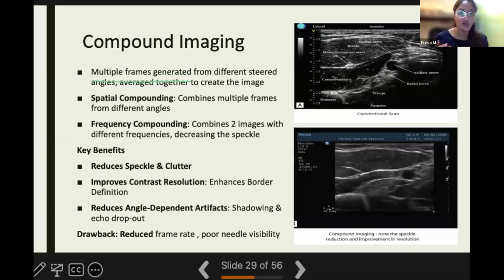So now compound imaging is of two types. We either have spatial compounding, which means that multiple frames are generated from beams that are being sent out at different angles, or we have frequency compounding, which means that you combine the images that are being produced by two different frequencies by the same ultrasound probe. So the first one is actually going to improve your contrast, and it will also reduce angle dependent artifacts, while the second, which is the frequency compounding, will reduce speckle and clutter, and it'll make your image look a lot smoother. So it'll reduce noise in your image.